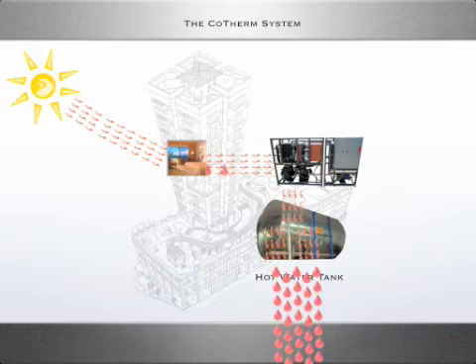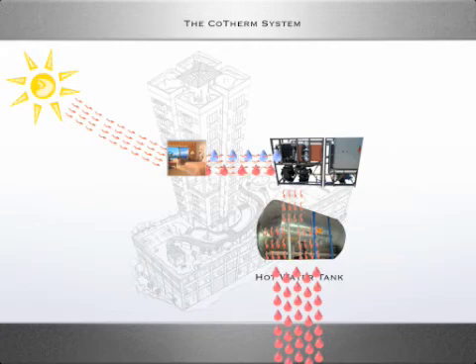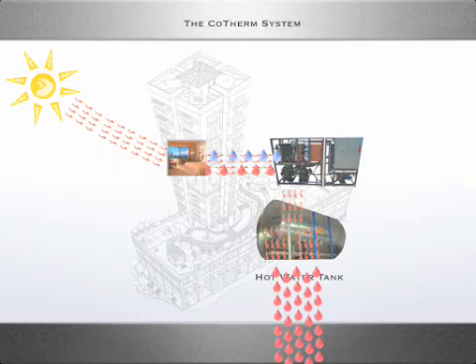You see, the heat is actually transferred through the air conditioning system in water. When the Cotherm removes the heat in the air conditioning, it is in essence removing the heat from the water. It then returns that cooled water back into the air conditioning system. By doing so, the Cotherm unit is reducing the load on the air conditioning system by 10-30%, so the air conditioning system is not working as hard. Therefore, the Cotherm electrical expense is offset by allowing the air conditioning system to work less, erasing the fuel bill for hot water without erasing the electricity bill.